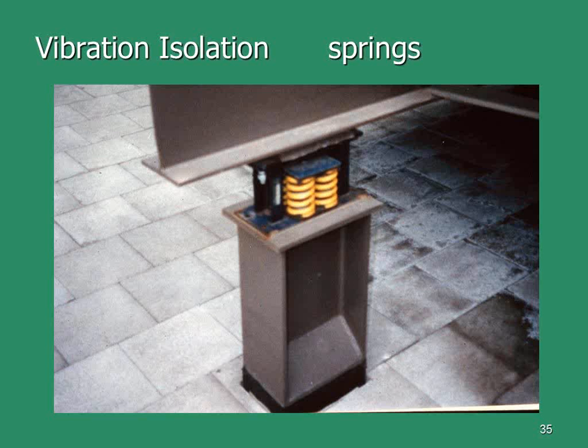You hear the noise conducted through the bone better than you can hear it conducted through your eardrum. If you do that and then go up on the roof and put your ear against a piece of equipment, you'll often hear those same tones. They're usually lower frequency, usually pure tones - something like the RPM of the fan wheel, the blade passage frequency. They're usually discrete tones, not just general broadband air noise.